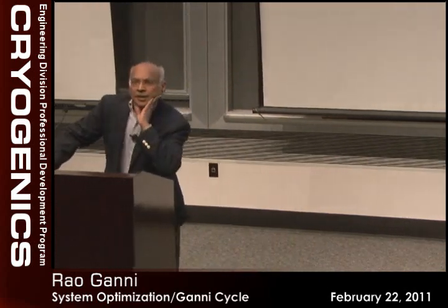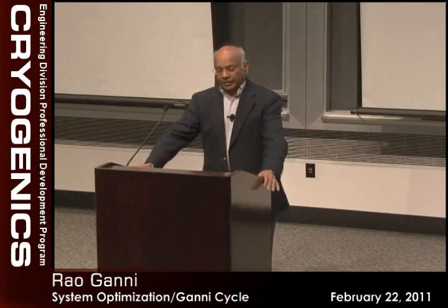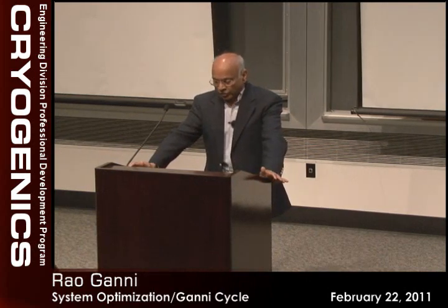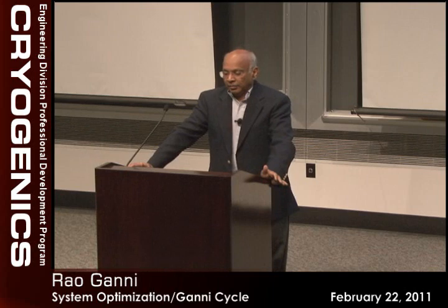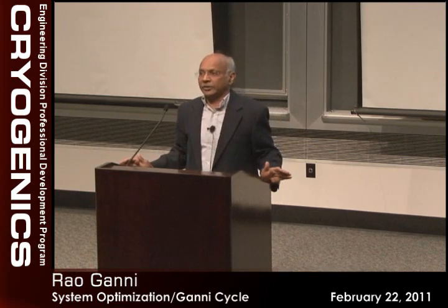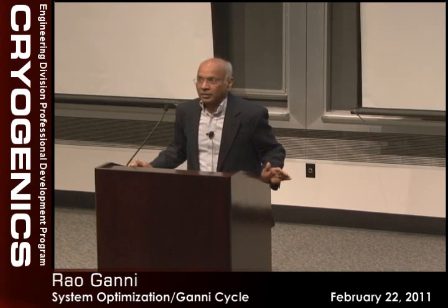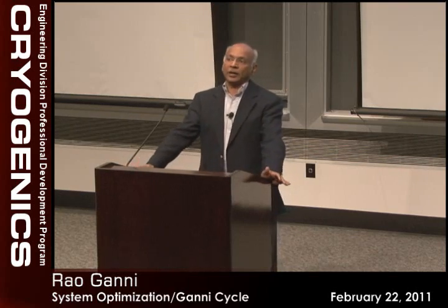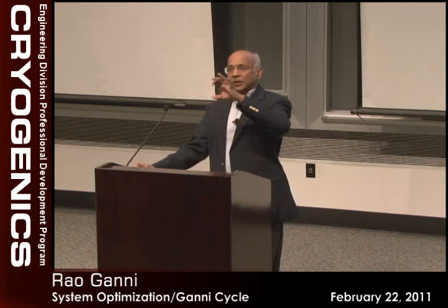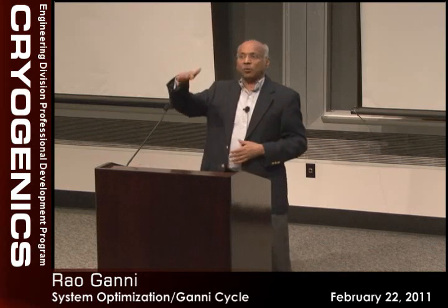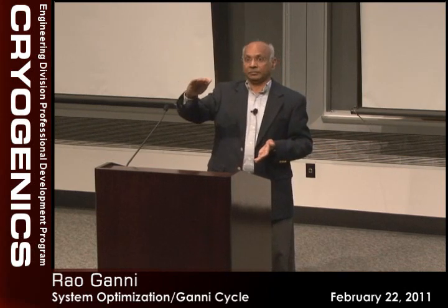You did that briefly, but you didn't really explain the thing about the turbines getting cold and also about the turbine speed. Could you briefly touch on that? Okay. One of the misnomers at JLab when I got here is that the turbine speed controls the capacity. Actually, for these turbines, the speed is independent of its capacity. They should be running at full speed if you can vary the brake. At CHL, the brake was fixed, so we were indirectly controlling the inlet pressure to the turbine. So the speed was coming down because the brake is fixed as we reduce the inlet pressure. If the brake was variable like ESR, where the turbine brake adjusts as the amount of output varies, the turbine will always run at one speed.